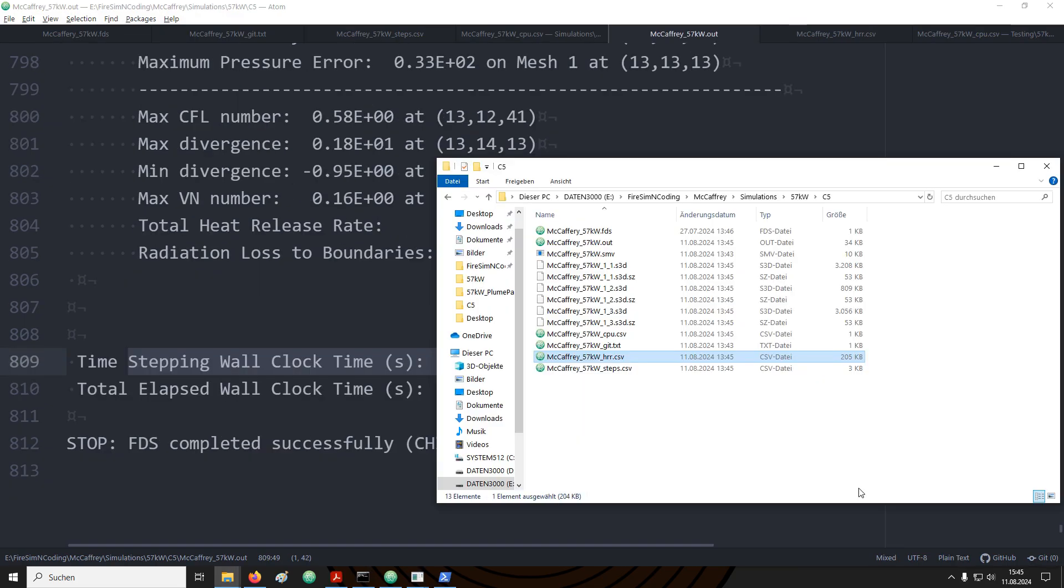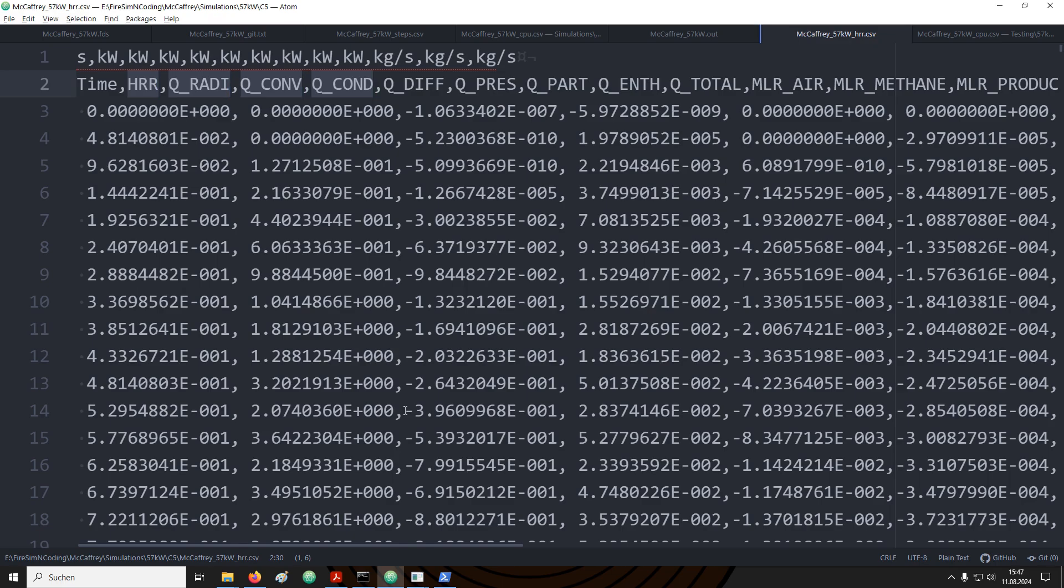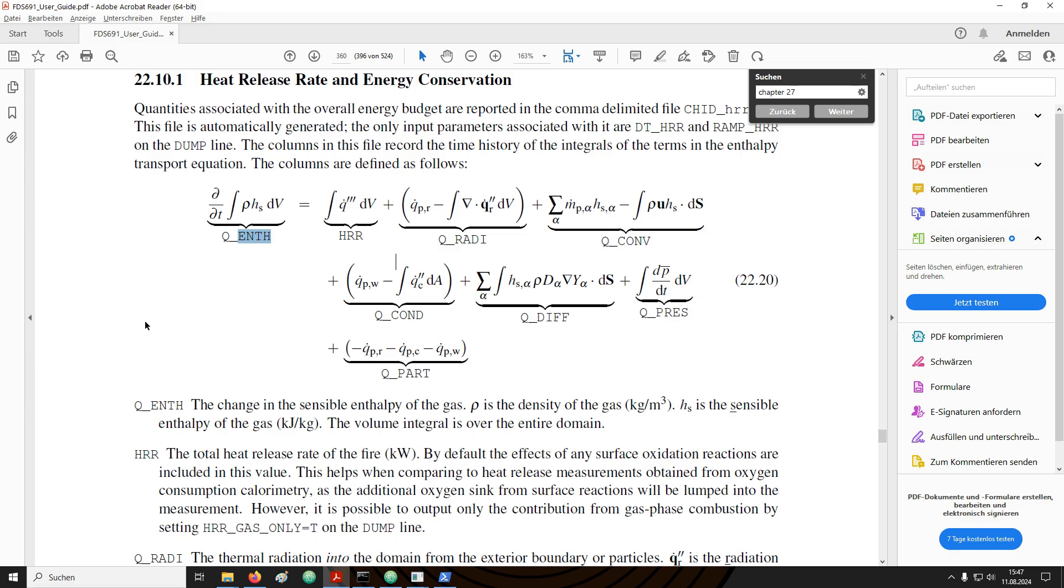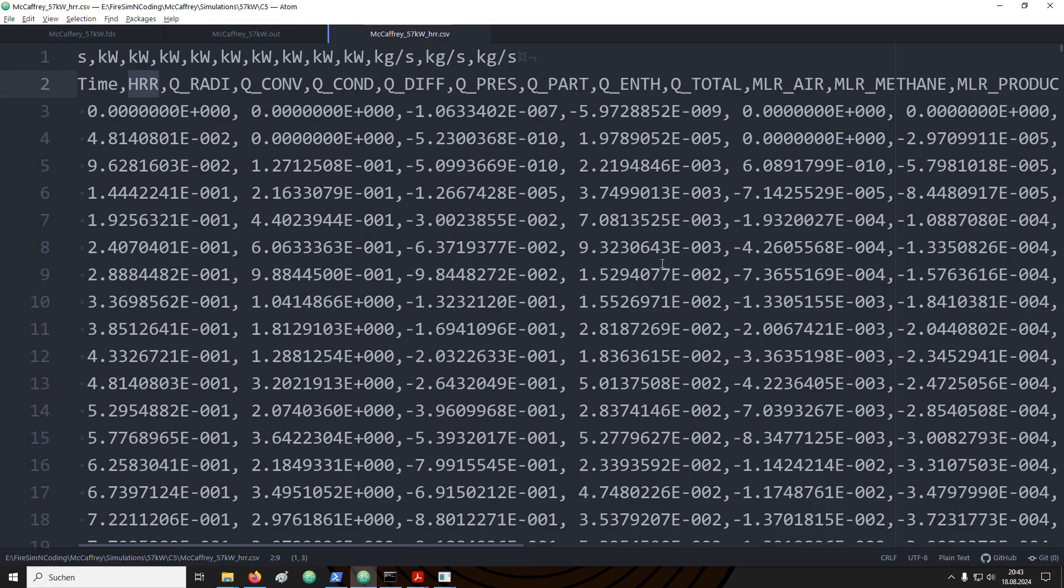Now, let's have a look at the HRR file. The HRR file contains information about the heat release and the energy conservation. You'll find more details on this in the section heat release rate and energy conservation in the user's guide. The terms on the right-hand side of equation 22.20 are provided in the HRR file. The columns after the time are the heat release rate, Q radiation, Q convection and so forth. There is further Q total, which is the sum of all terms on the right-hand side. The value for the sensible enthalpy should be the same as the sum of all the terms on the right-hand side. We can plot the enthalpy change over the course of the simulation. If we plot Q total into the same plot, we should see that they are basically overlapping, which is the case here. Furthermore, we could also sum up all the individual components, which should be equal to Q total and also overlap with the rest, which it does.